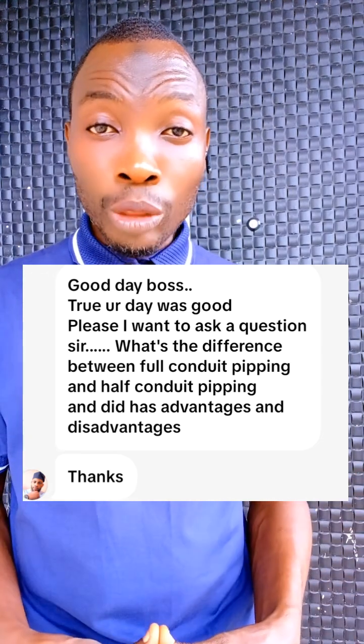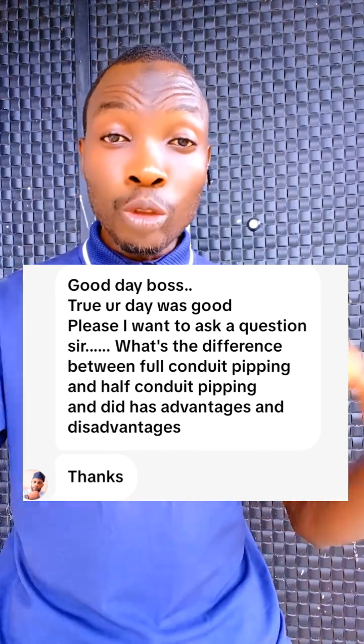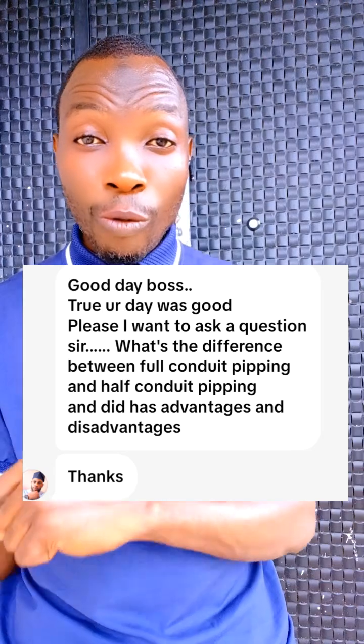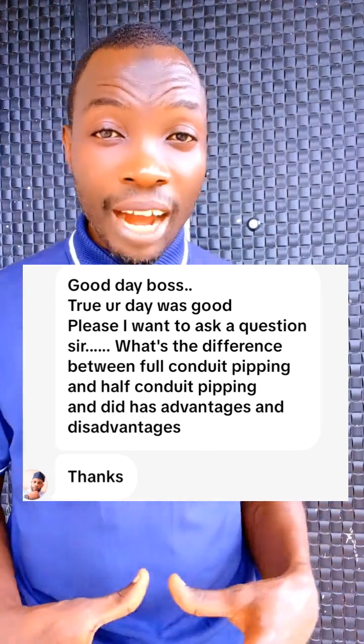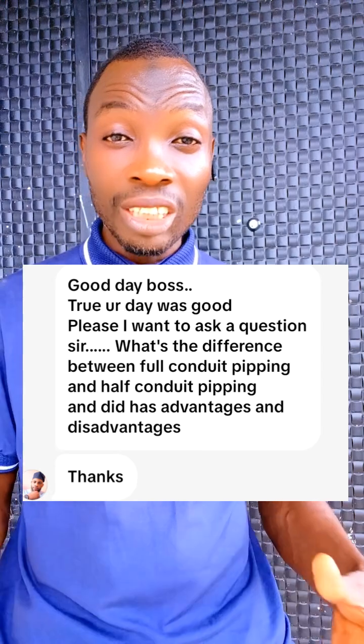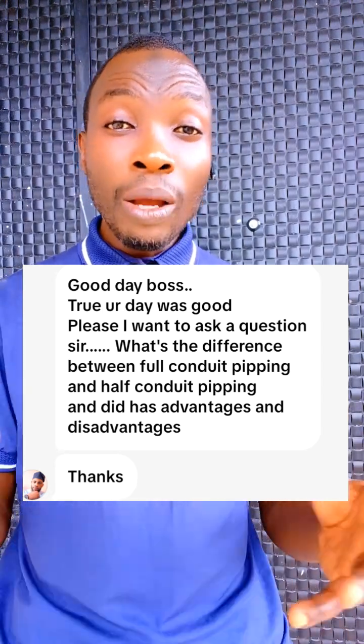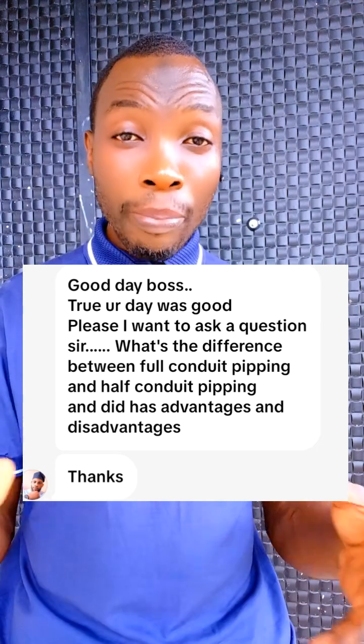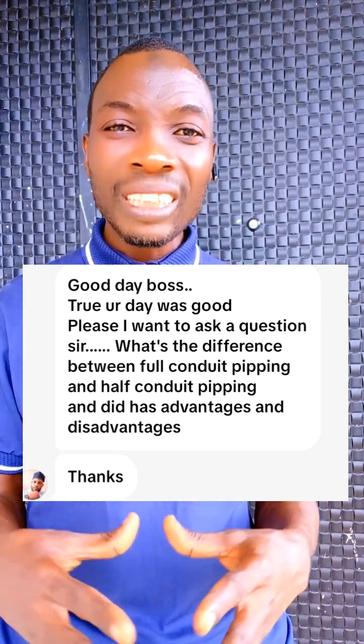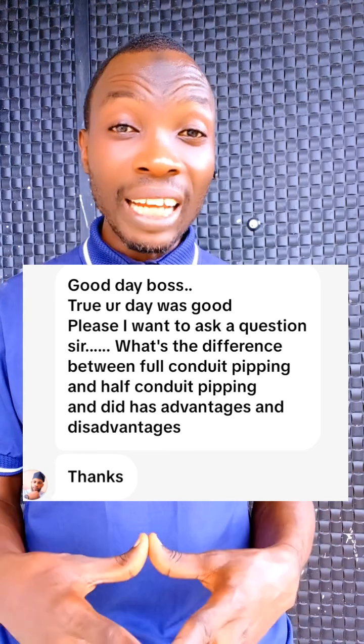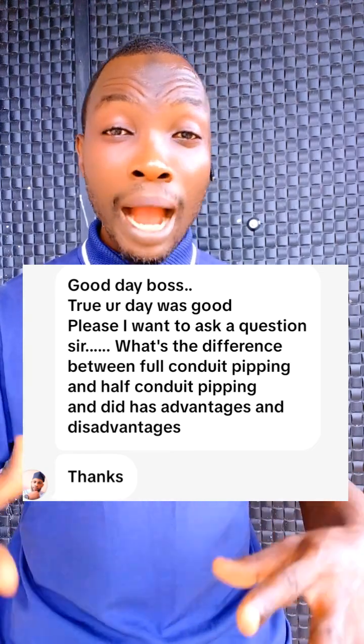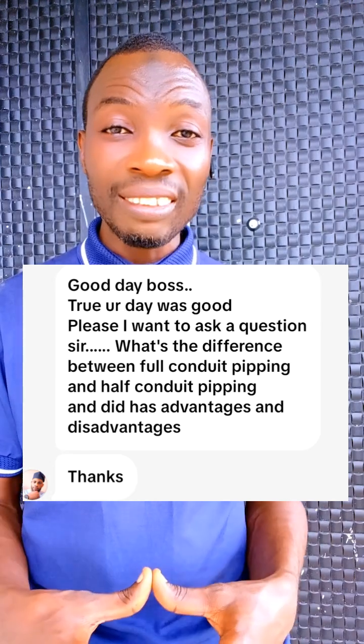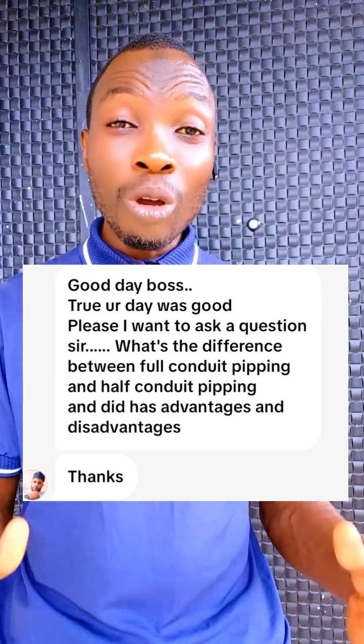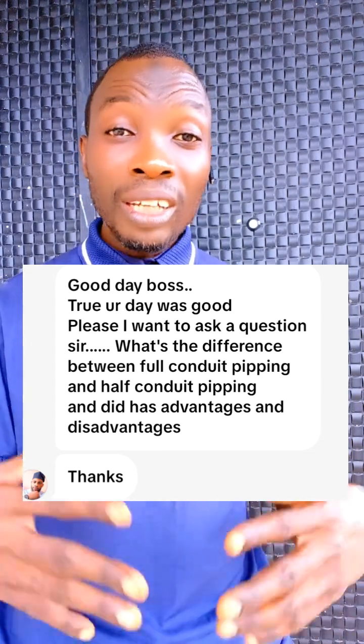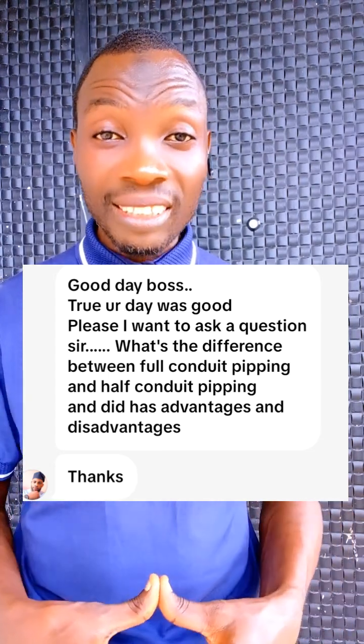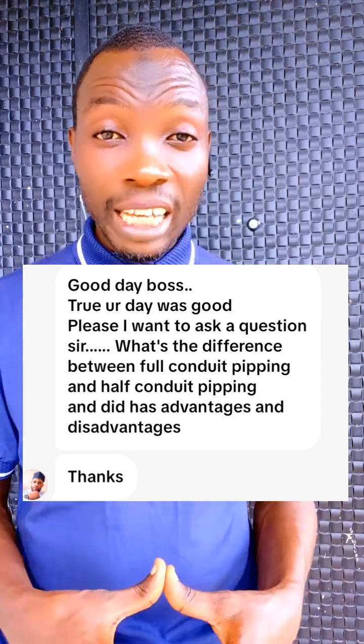But if it is half conduit, you still need to go into the roof to remove the cable for replacement. Another beautiful advantage is that cables, when concealed in pipes, are safer. They have a constant ambient temperature in most cases. But when you leave your cable in the roof, even the day temperature affects the temperature surrounding the cable.